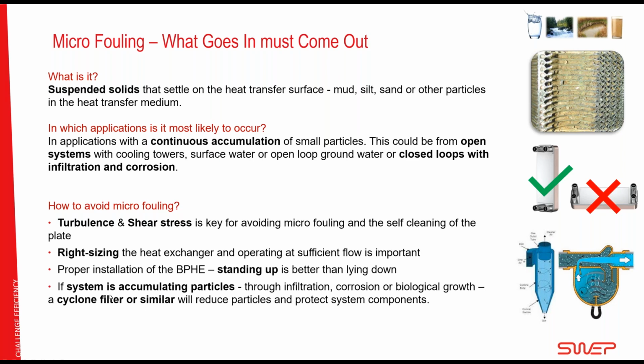So if the system is accumulating particles, if you're any one of these, the closed loop with infiltration or an open loop, consider using a filter, a cyclone filter or a bleed off filter, so that you can control the total concentration of suspended particles. The more you have of the suspended particles, the more you will have a risk of it accumulating in key parts of the system, heat exchangers, pumps, everywhere.